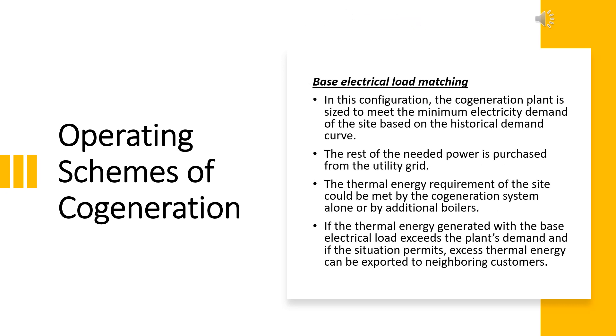The first scheme is base electrical load matching. The co-generation plant meets the minimum electricity demand. If we have a minimum demand, the maximum demand is met by the utility grid. Thermal energy from the co-generation system and additional boilers is generated with the minimum electrical load. Excess thermal energy can be exported to neighboring customers.